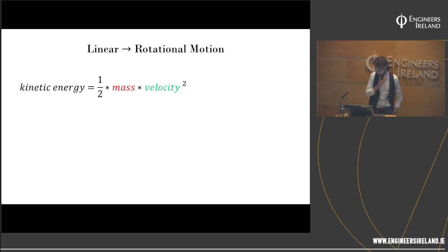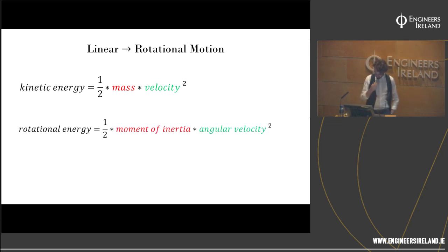To start off, I'm going to bring you back to your secondary school physics class, and that equation that you've seen before. Kinetic energy is half times the mass multiplied by the velocity squared. Now this term for kinetic energy can be mapped to the rotational frame, which is what we're interested in when it comes to conventional synchronous generators rotating when they're connected to the grid. An analogous equation for kinetic energy in the linear time frame is rotational energy, which is a half times the moment of inertia times angular velocity squared. So we can see that the moment of inertia is taking the role of the mass, and the angular velocity, the rotational speed, is taking the role of velocity in a linear frame. And this rotational energy is what is colloquially termed inertia.